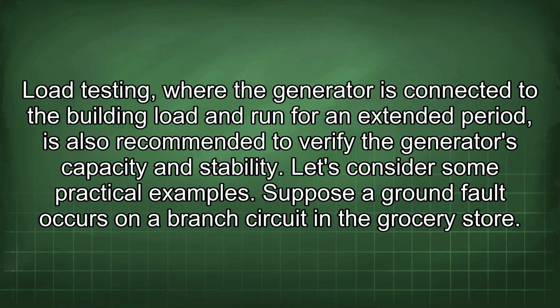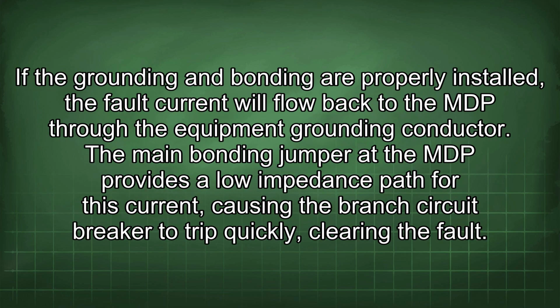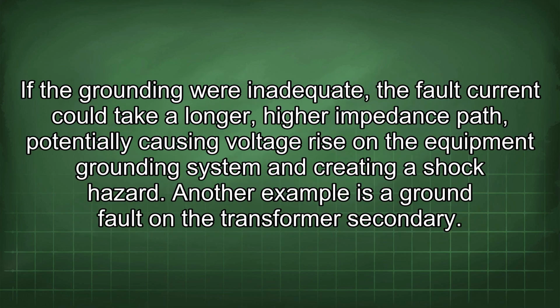Let's consider some practical examples. Suppose a ground fault occurs on a branch circuit in the grocery store. If the grounding and bonding are properly installed, the fault current will flow back to the MDP through the equipment grounding conductor. The main bonding jumper at the MDP provides a low impedance path for this current, causing the branch circuit breaker to trip quickly, clearing the fault. If the grounding were inadequate, the fault current could take a longer, higher impedance path, potentially causing voltage rise in the equipment grounding system and creating a shock hazard.